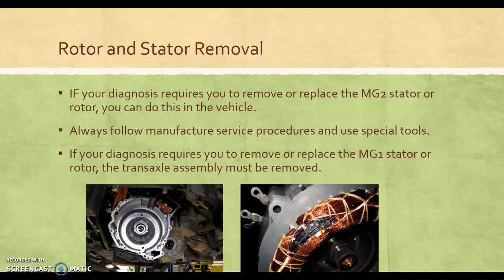But you look at this picture, you can see that burnt winding. You'll see that on your insulation tests and more than likely your phase-to-phase balancing. So use those tools and those tests heavily in your field. It'll save you time before you have to pull apart transaxles, and it does give you a confirmation on whether or not it's good. So little nudge, push test, those two tests, and you look like a star. Combined with your PPE, your gloves, your tooling, and your meter, then you are set, ready to roll.